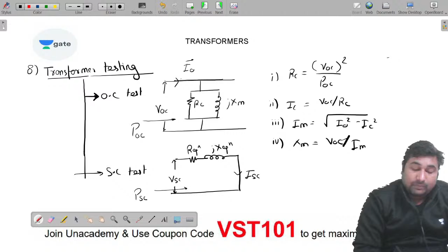The electrical equivalent model under short circuit test can be represented in this way for the transformer, where we have R equivalent, X equivalent, and the current flowing is the short circuit current ISC, with voltage VSC. We always use a reduced voltage which is just sufficient to cause rated current under the short circuit test. If the test is conducted at rated current, it gives rated copper loss.